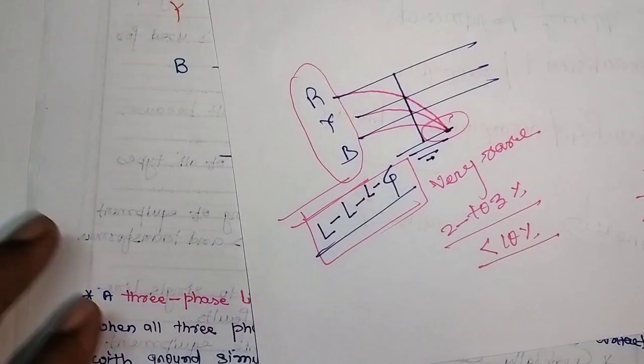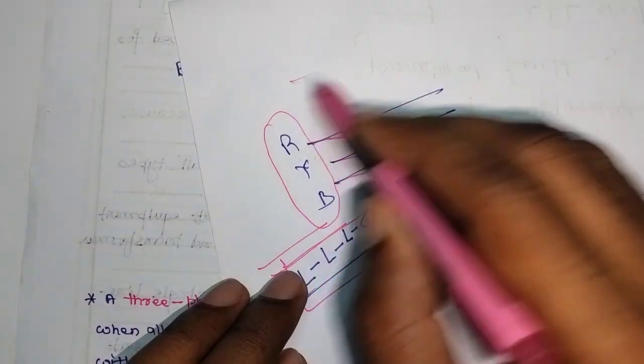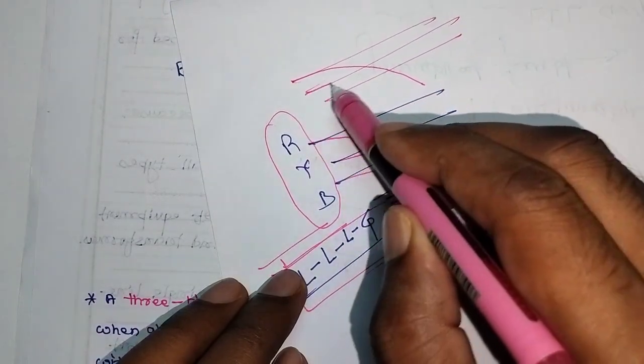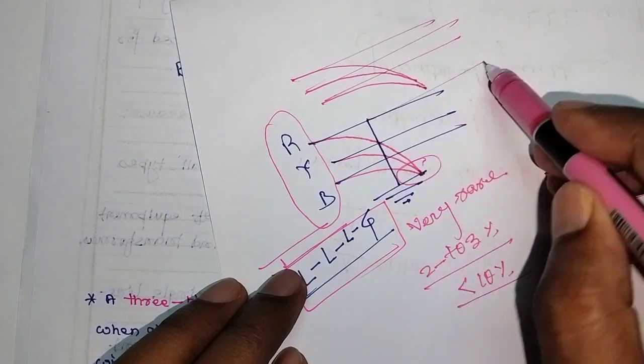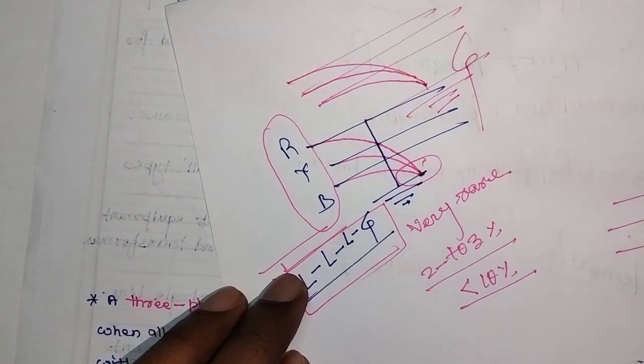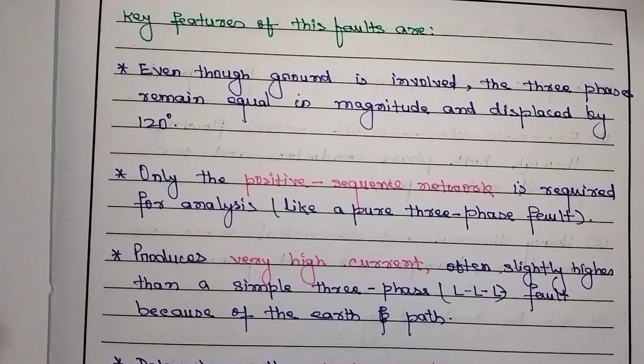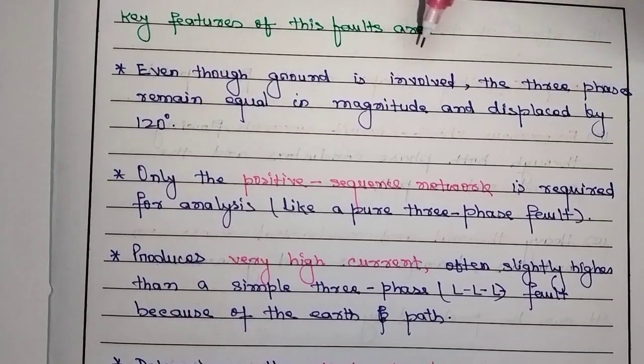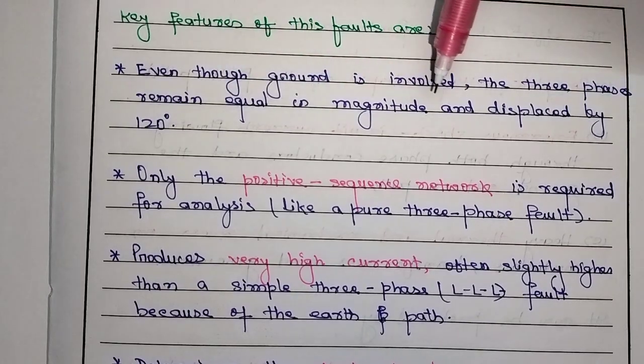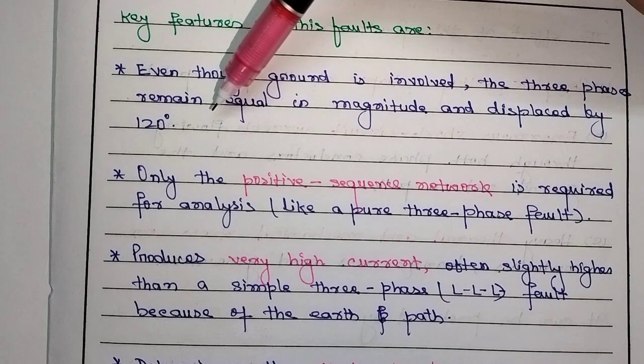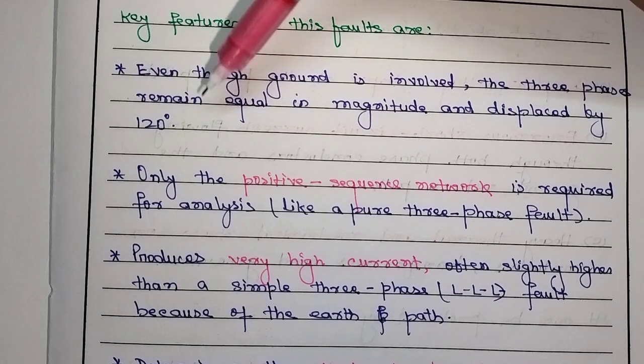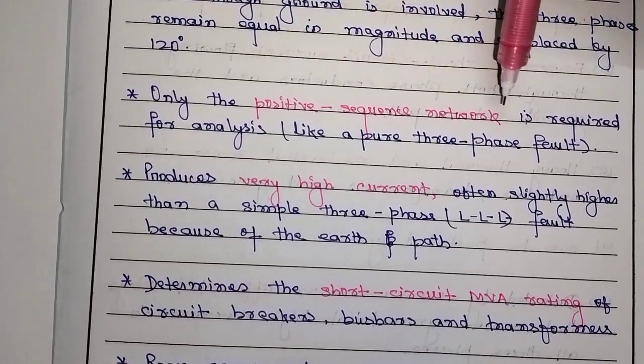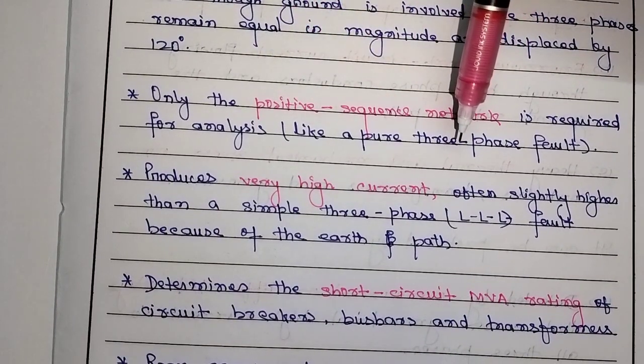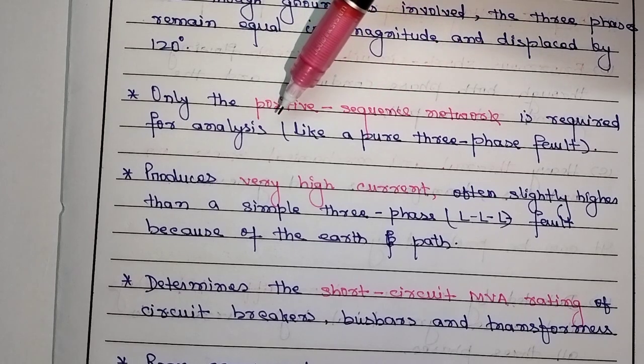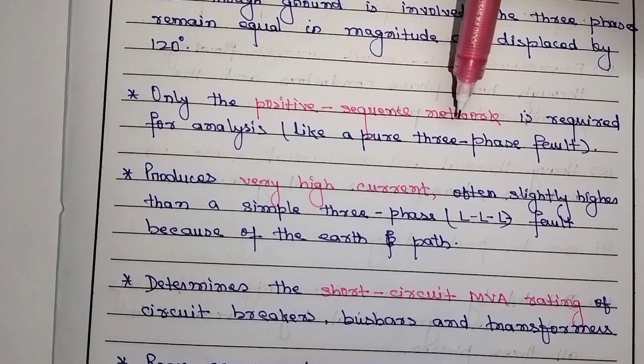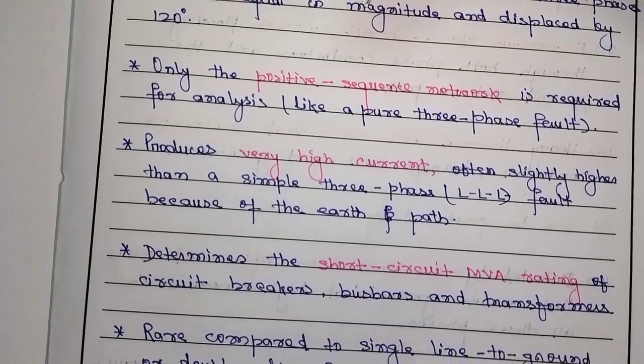In the diagram also I have shown that whenever the fault occurs in the system, all of them, after the breakage, touch the ground at the same point only. The key features of this fault are, even though ground is involved, the three phases remain equal in magnitude and displaced by 120 degrees, the same as we have seen in the line to line fault. Only the positive sequence network is required for the analysis, like a pure three-phase fault. Already we have discussed in the last section that we require only the positive sequence network for the analysis of the three-phase fault whenever it occurs.